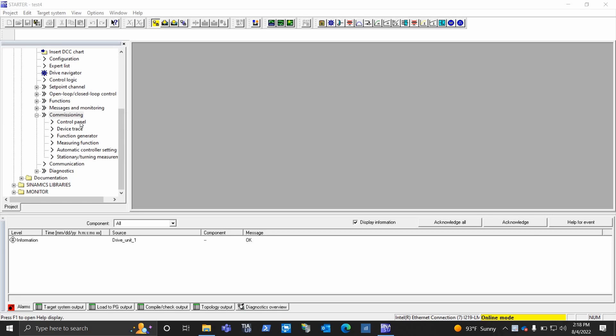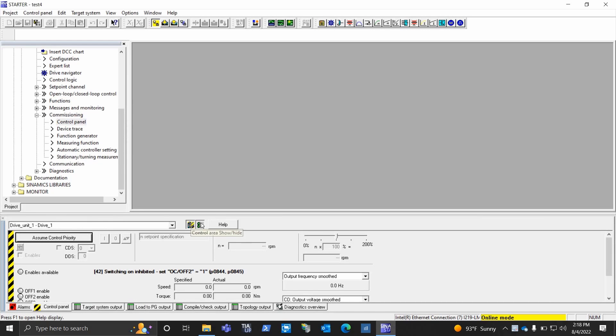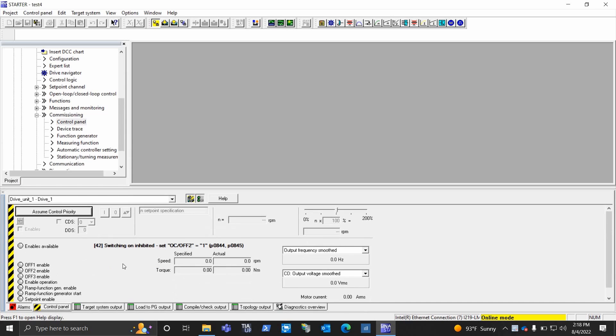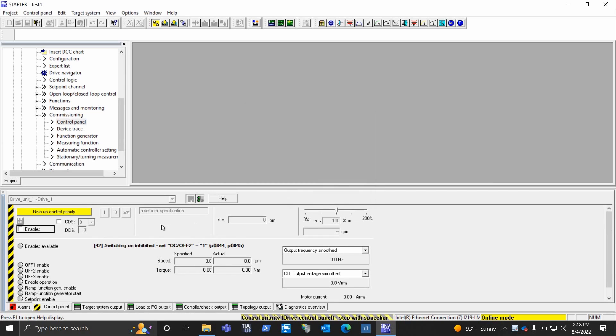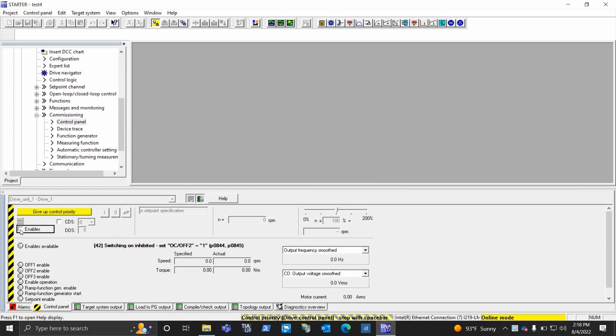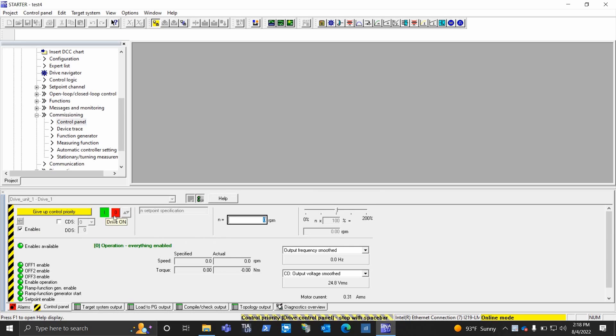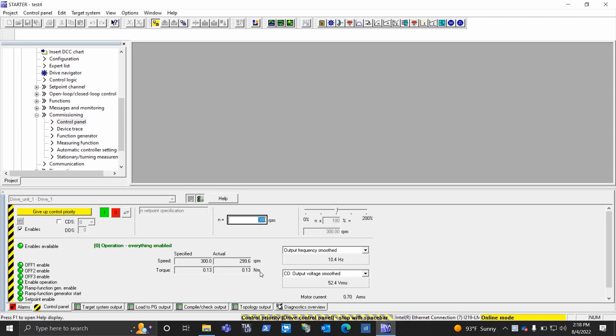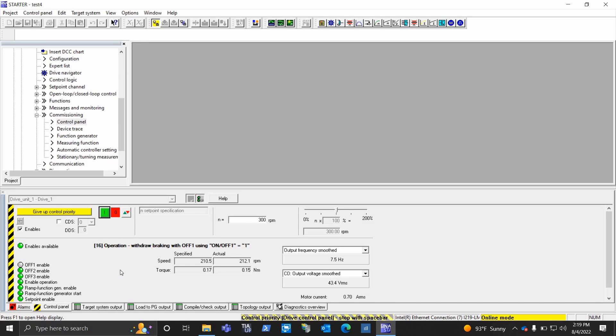Now you may want to just test your motor now that you've tuned it. You just want to run it by itself. You just go to the commissioning control panel, same place we kind of were for the stationary tuning and measurements. Try to get this to come up here, there we go. So we're going to do the same thing, except for now we're going to be able to just manually give it a speed and tell it to run once we do the enables. And again, make sure there's personnel safety, and if there's a loop pump or something and it has to be turned on, make sure that's running before you do this. I'm just going to say, hey, run at 300 RPM. It ramps up to 300 RPM. It gives you the frequency, the current it's pulling, the torque that it's pulling. So it's a good way to quickly check if everything's good.